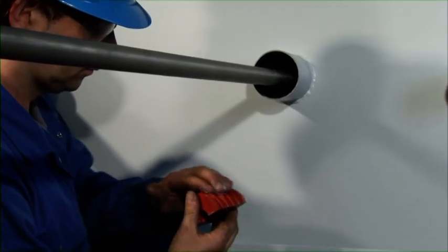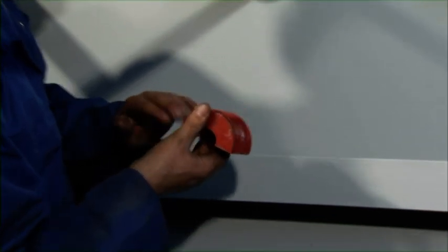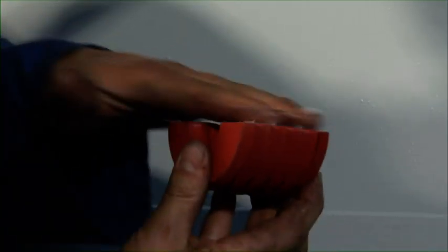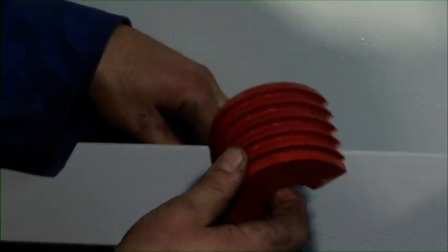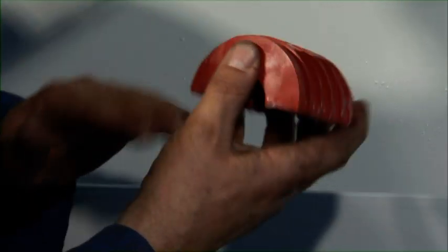Next, both parts of the dynatite plug are lubricated on the inner side, including the connecting surfaces, as well as on the outer surface and the serration. Always use sufficient lubricant. This eases the installation significantly and thus enables optimum sealing.